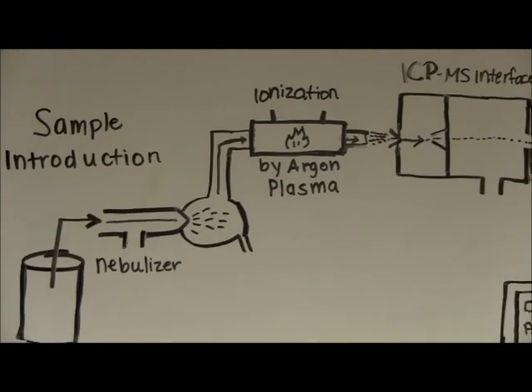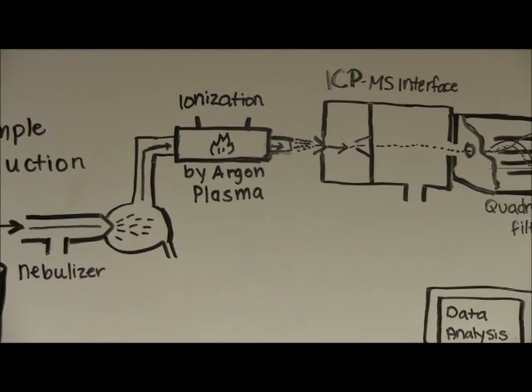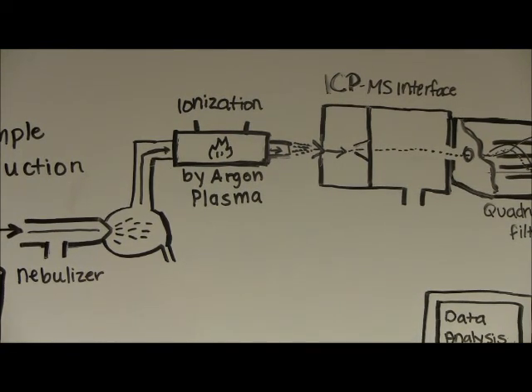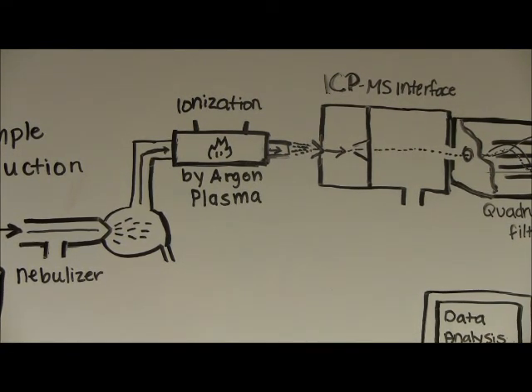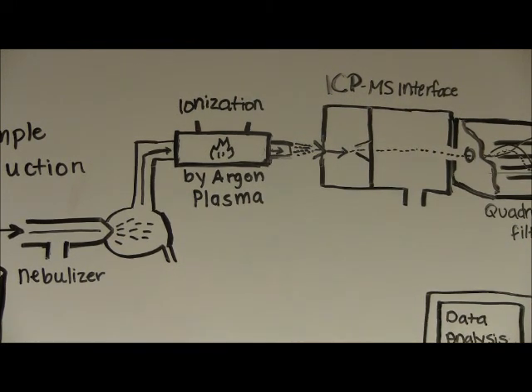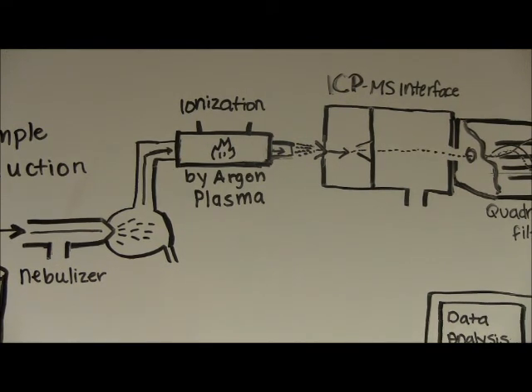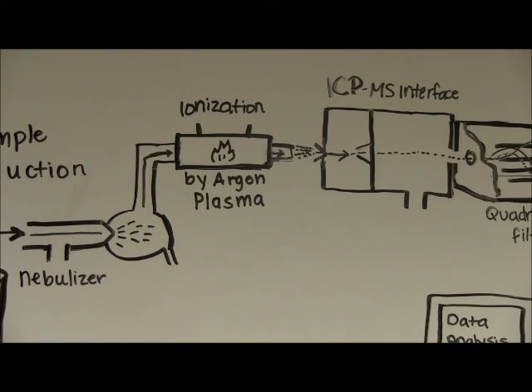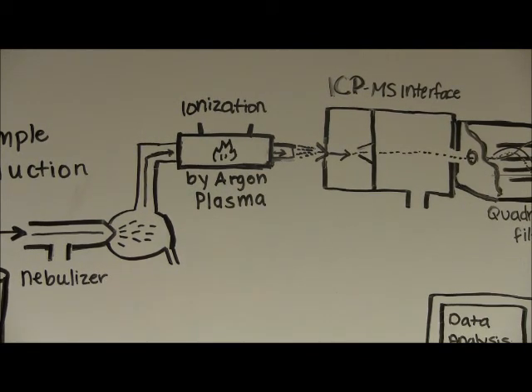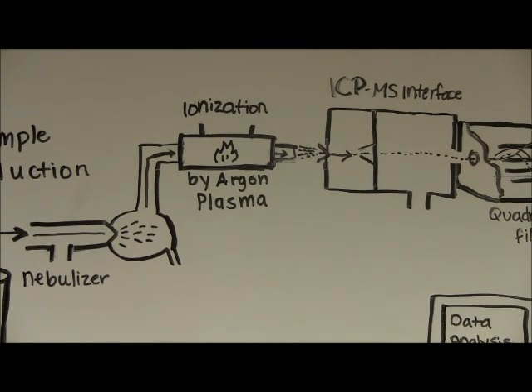Once the sample passes through the nebulizer and is partially desolvated, the aerosol moves into a torch body and is mixed with more argon gas. A coupling coil is used to transmit radio frequency to the heated argon gas producing an argon plasma flame located at the torch. The hot plasma removes any remaining solvent and causes sample atomization followed by ionization. In addition to being ionized, sample atoms are excited in the hot plasma, a phenomenon on which ICP atomic emission spectroscopy is based.